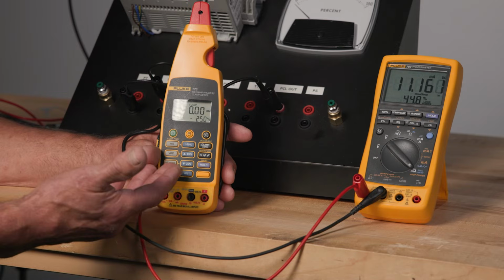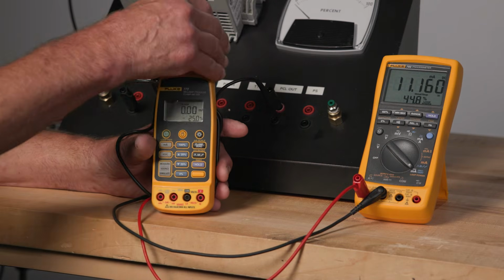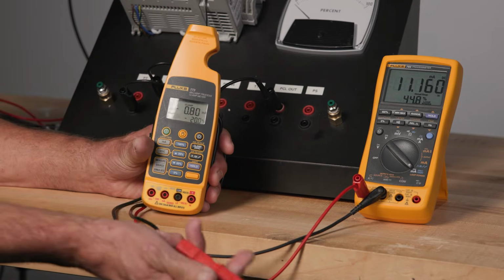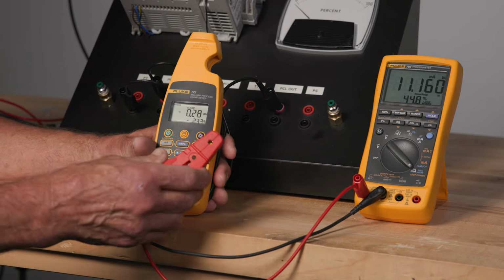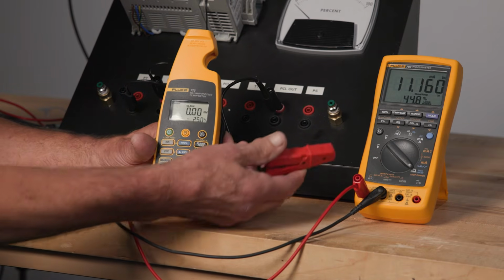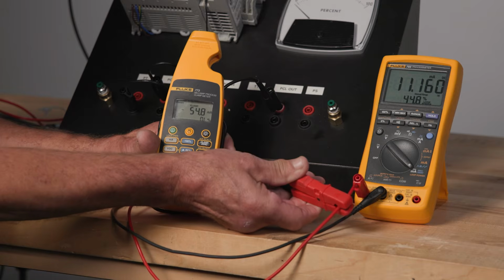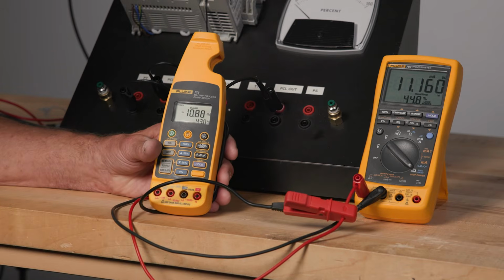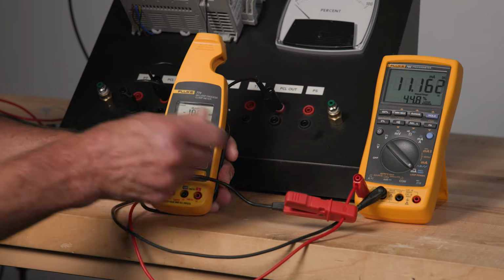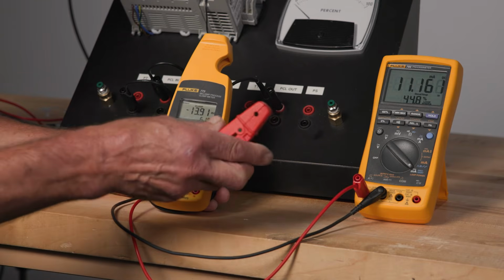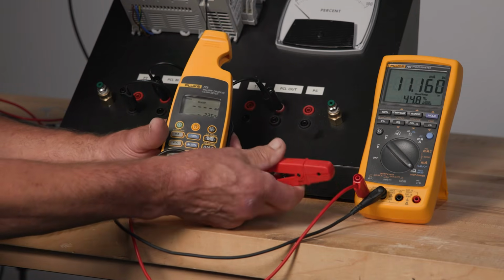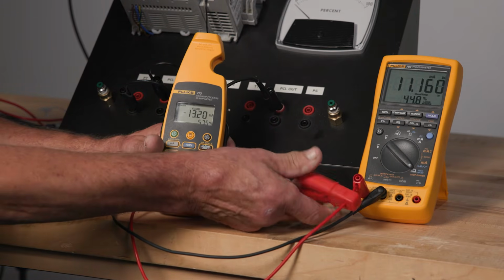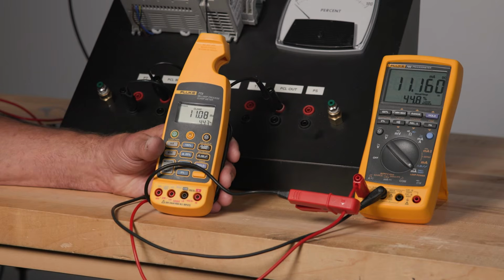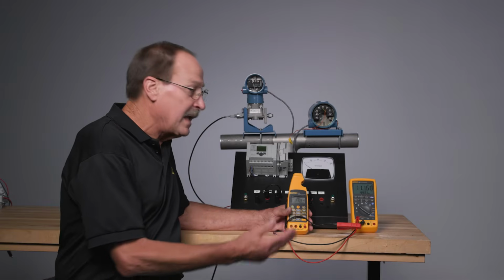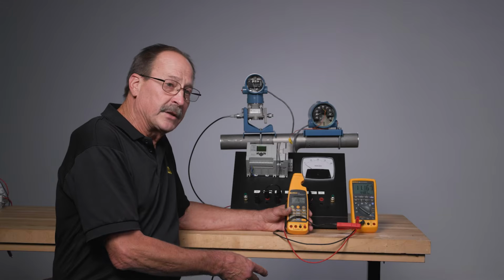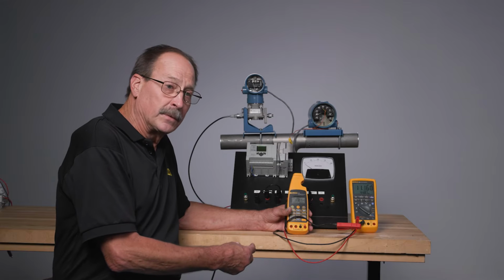The Fluke 773 Milliamp Clamp Meter is a combination of a milliamp measurement tool using the clamp. For example, I have a milliamp signal here, and I connect the clamp, and I can see the milliamp signal that I'm measuring. If I want to change the polarity of the measurement, I can turn it around and make the measurement like this. So this allows you to make milliamp measurements without breaking the loop and interrupting process control.